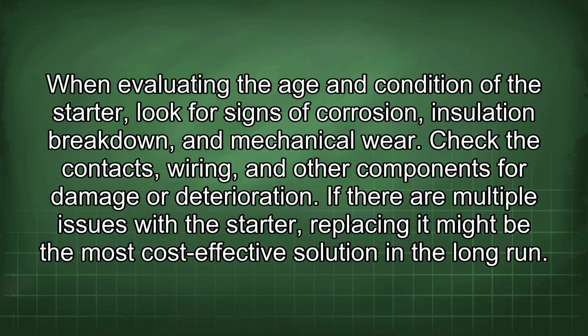When evaluating the age and condition of the starter, look for signs of corrosion, insulation breakdown, and mechanical wear. Check the contacts, wiring, and other components for damage or deterioration. If there are multiple issues with the starter, replacing it might be the most cost-effective solution in the long run.